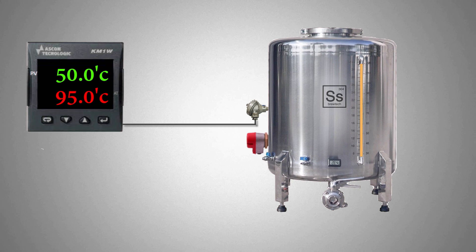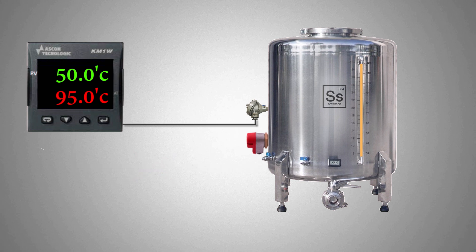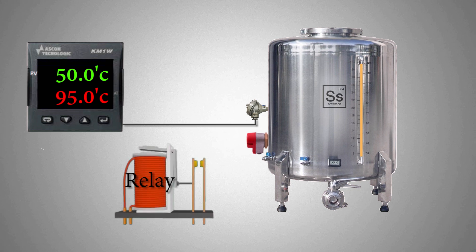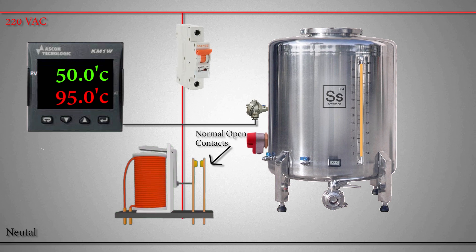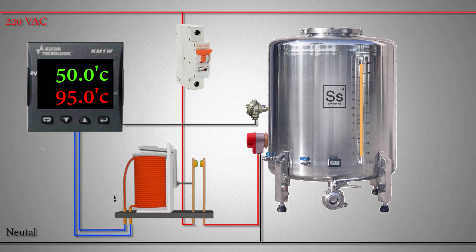We cannot connect the heater directly to the temperature controller. To turn on and off the heater, we need some switching device. We can use a relay or a contactor to switch the heater on and off. The relay's normally open contacts can be used to switch on and off the heater. The relay's normally open contact will be connected in series with the heater and voltage source, and the relay coil will be connected to the temperature controller. Now the temperature controller can turn on the relay, and the relay contacts close to apply voltage to the heater.